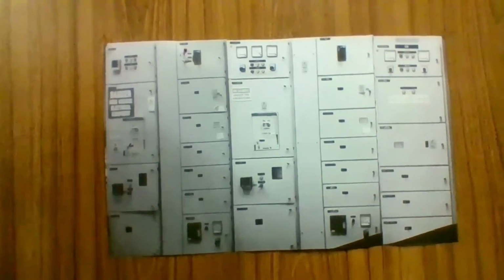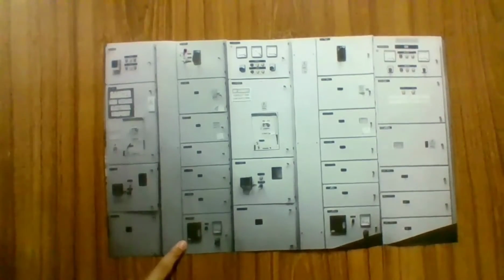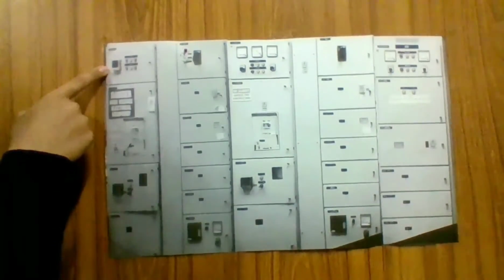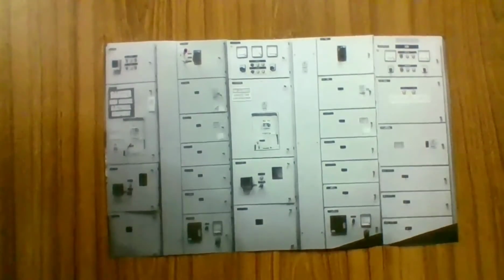Then we need to turn off the power factor capacitor bank. After that, check the current status at the ammeter to verify the presence of power supply. The current should be 0 ampere because there is no current flow after we cut off the power factor capacitor bank and the load.